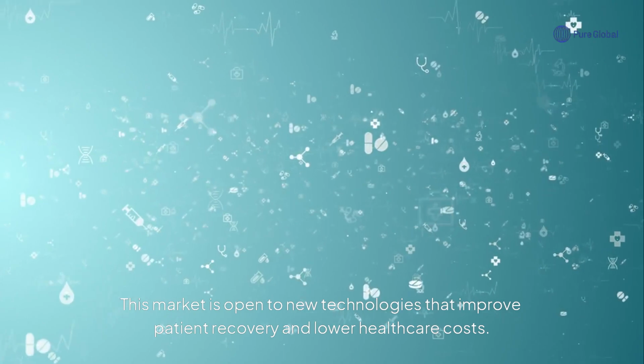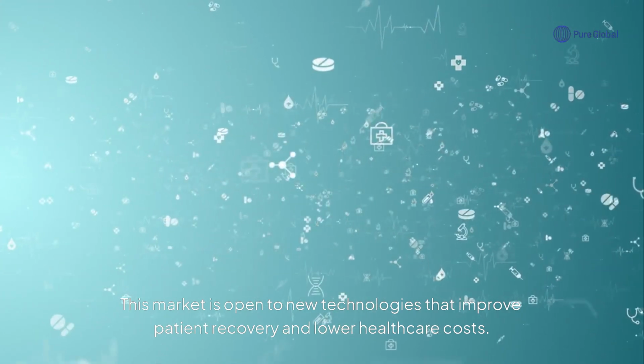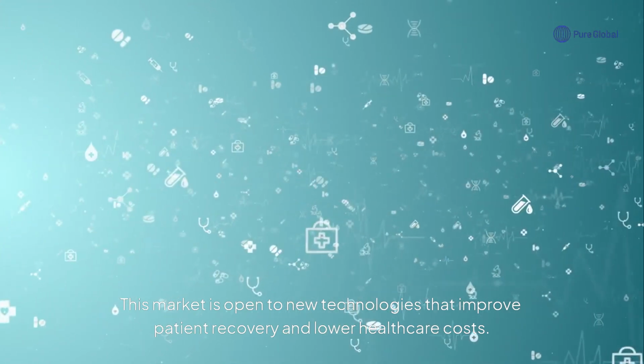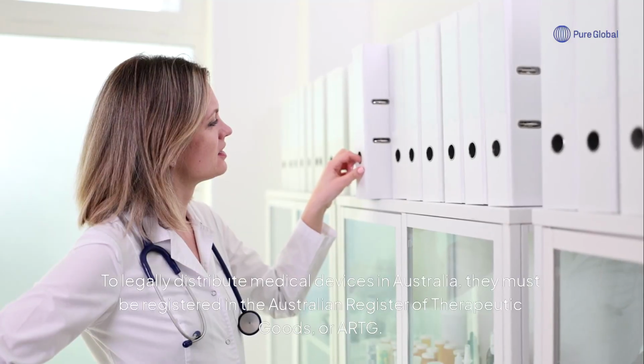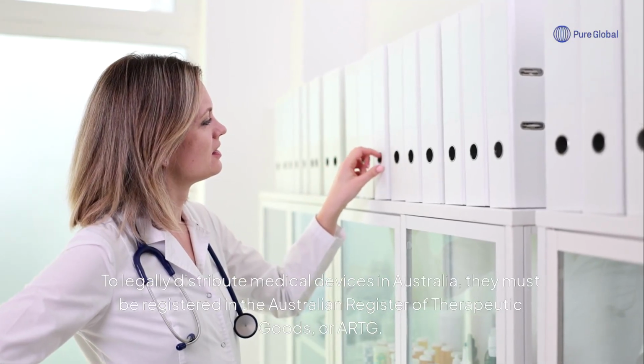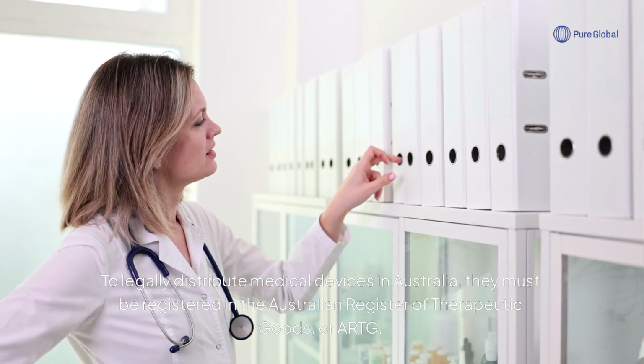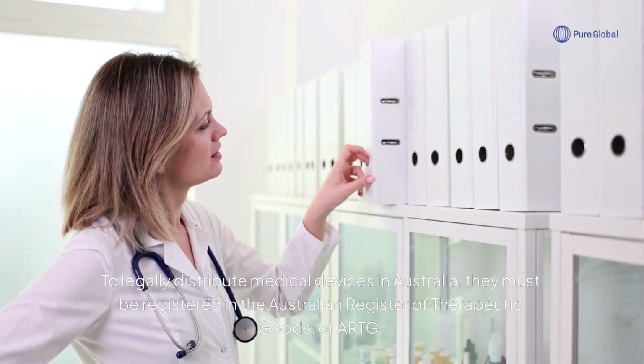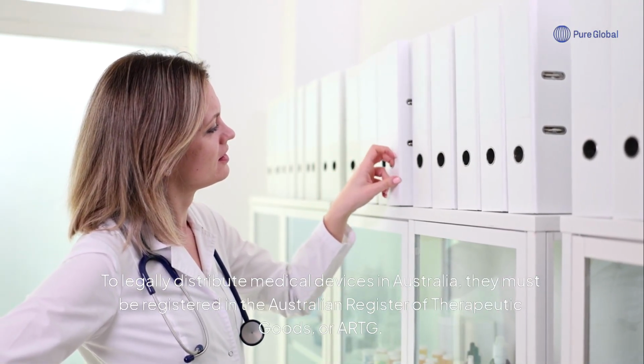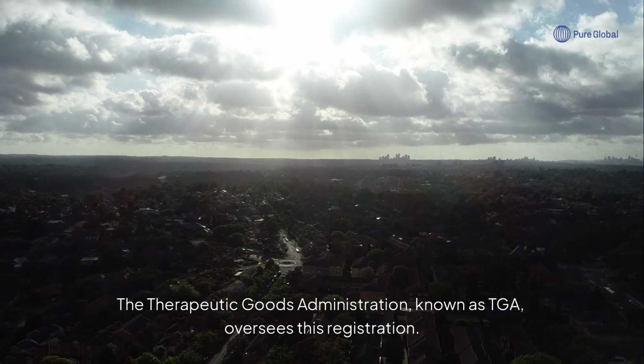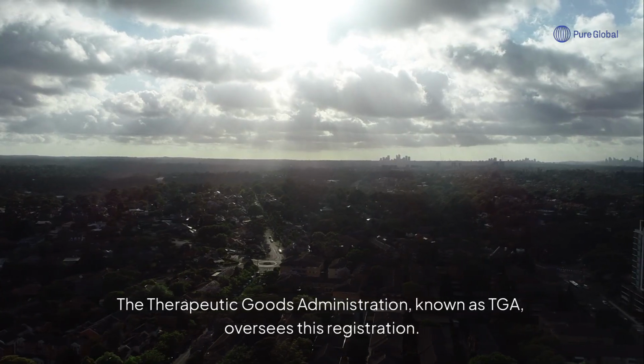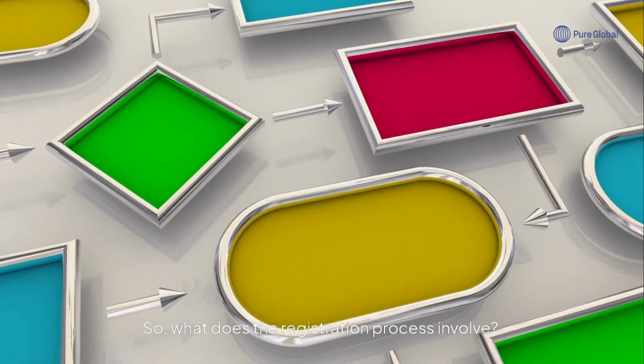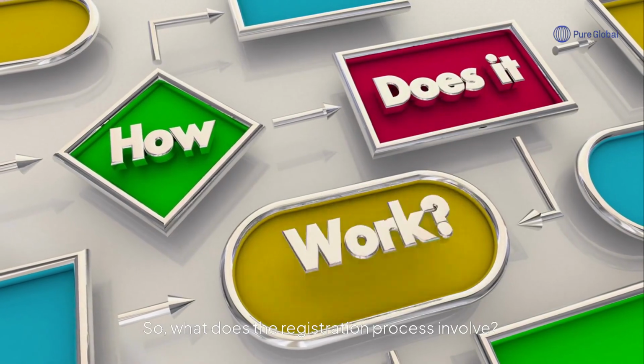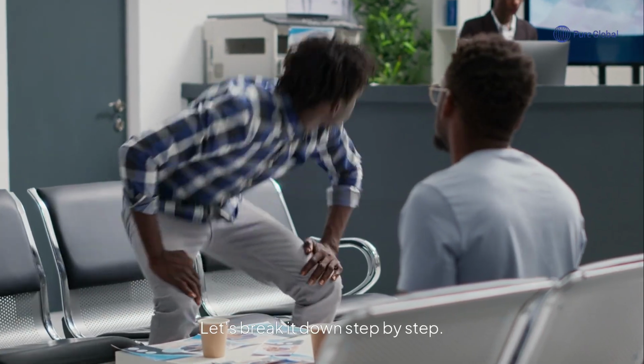This market is open to new technologies that improve patient recovery and lower healthcare costs. To legally distribute medical devices in Australia, they must be registered in the Australian Register of Therapeutic Goods, or ARTG. The Therapeutic Goods Administration, known as TGA, oversees this registration. So, what does the registration process involve? Let's break it down step by step.